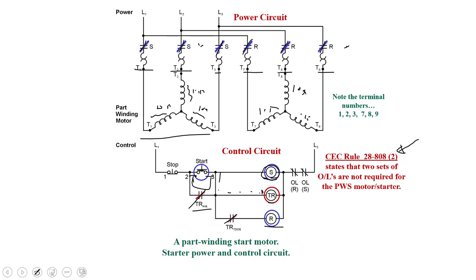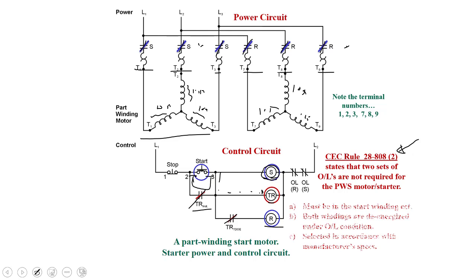So you basically are going to divide that current up in two, whatever the FLA is, and then you're going to size your overloads according to that and your service factor. Okay, so here are the rules. It must be in the start winding. Both windings are de-energized under overload conditions and selected in accordance with the manufacturer's specs. So those are the three things that 2808 will talk about.